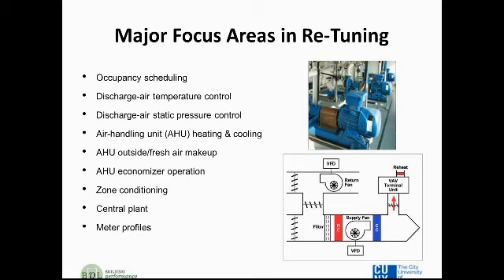Coming in from the lower left-hand side would be your outside air. Coming down from the top would be your return air, that would mix with your outside air, where that word filter is, to give you your mixed air. And then, of course, on the top left you've got a spill damper. That would, if you have any incoming air, you've got to balance.